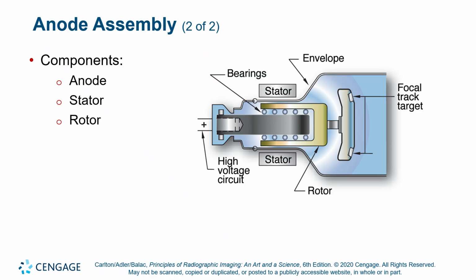Now the focal track is made out of, again, tungsten, but most of the anode is made out of molybdenum and graphite. The anode stem is usually made out of molybdenum. The molybdenum and the graphite connected to the back of the anode act as a heat sink for the tungsten focal spot. So both the molybdenum and the graphite will absorb and pull heat away from the tungsten, such that the focal spot doesn't overheat.